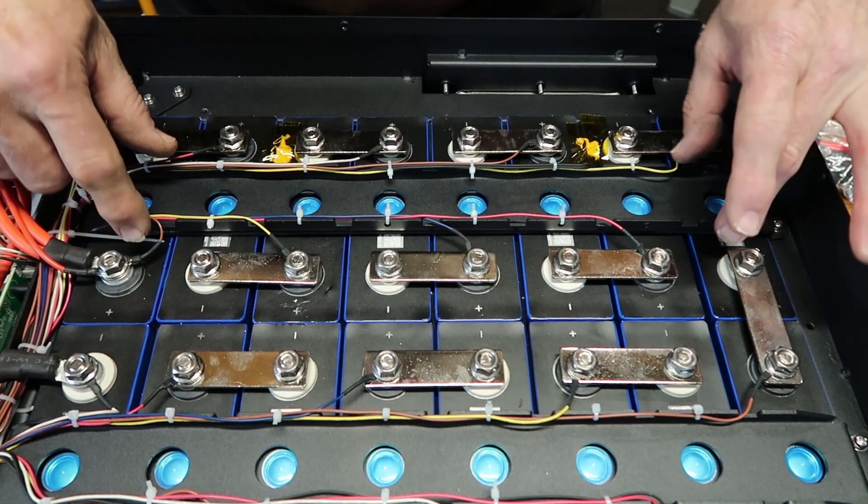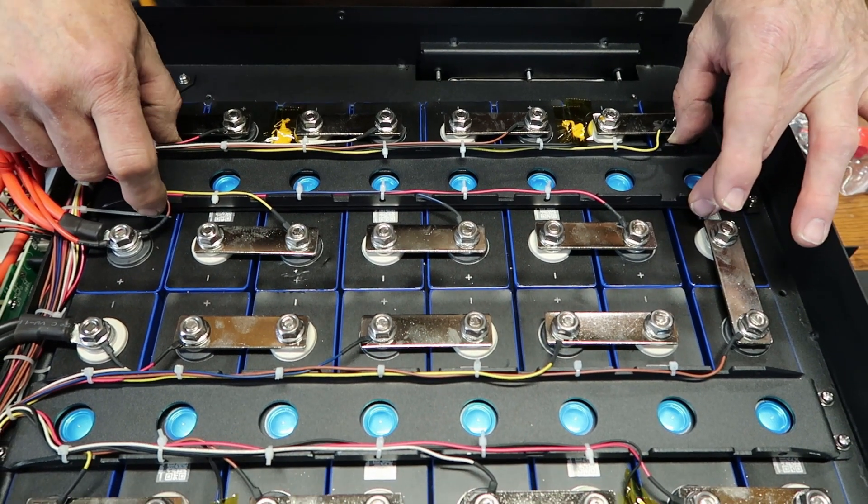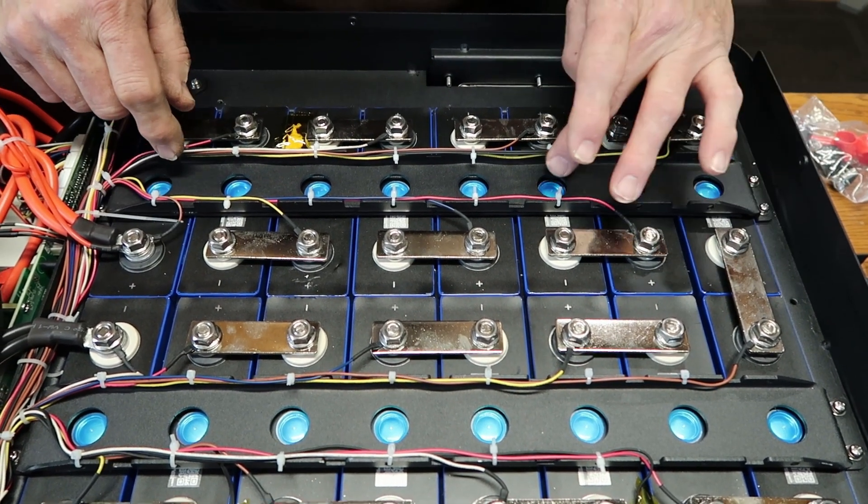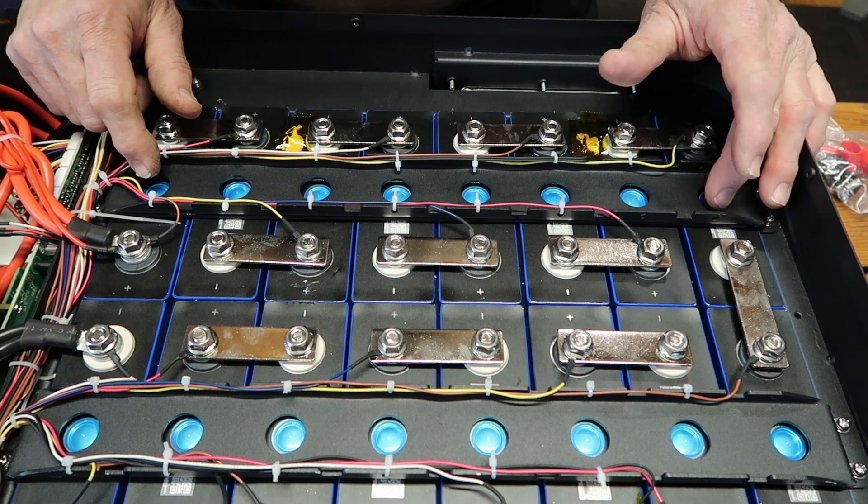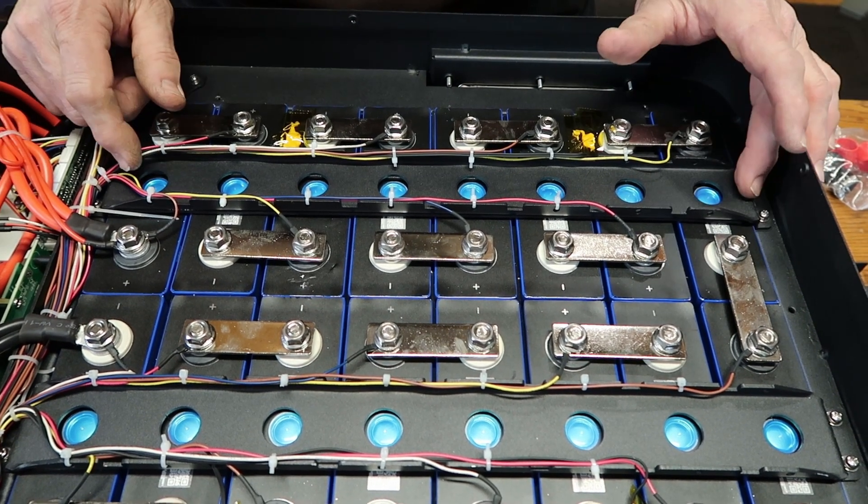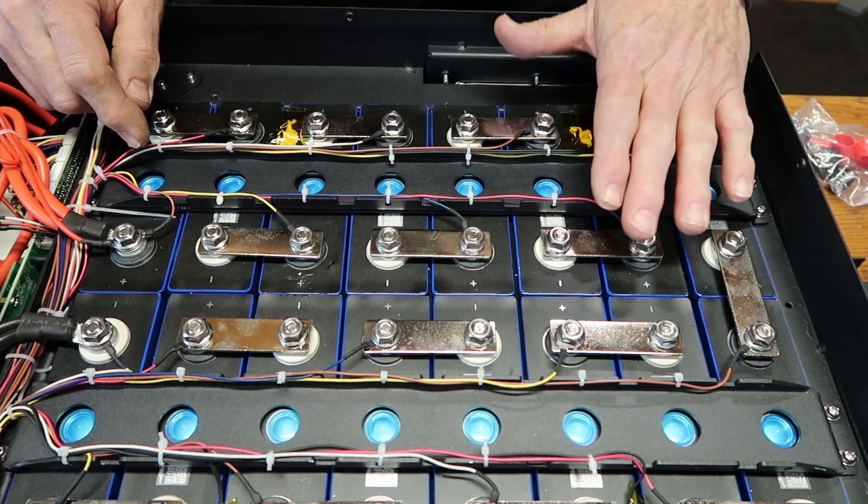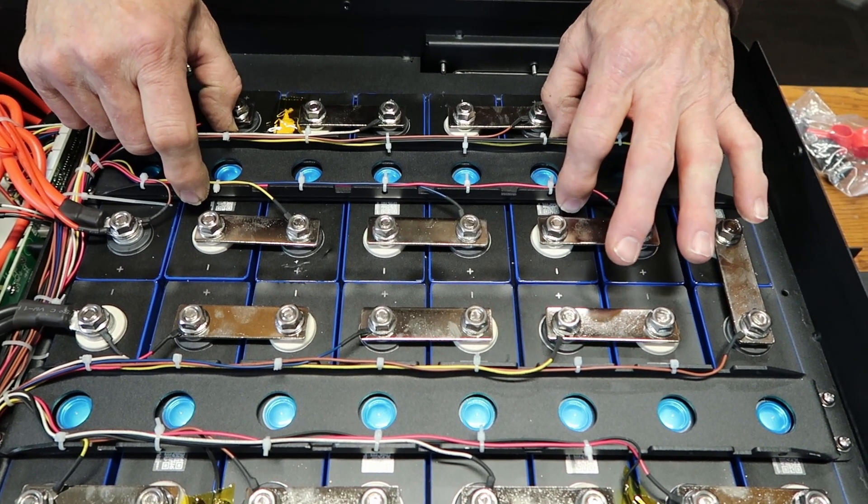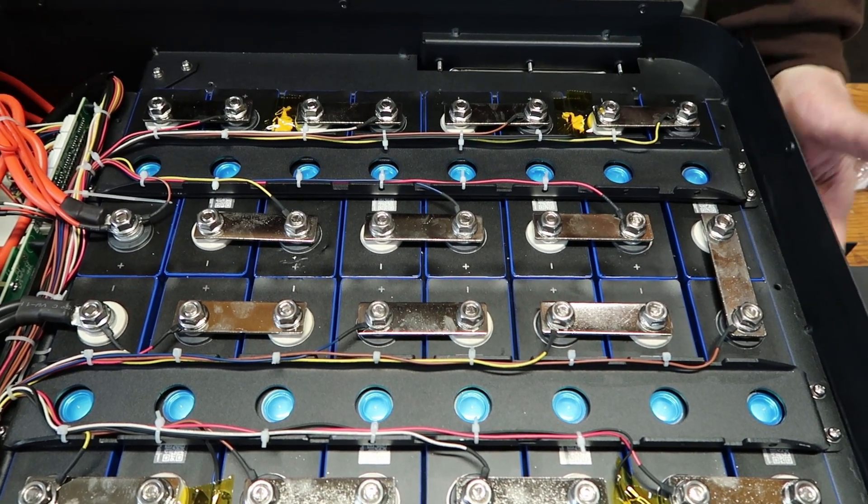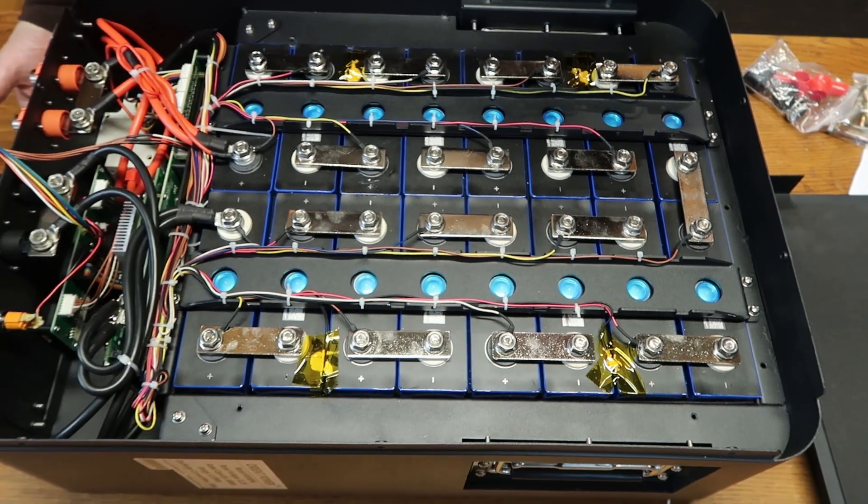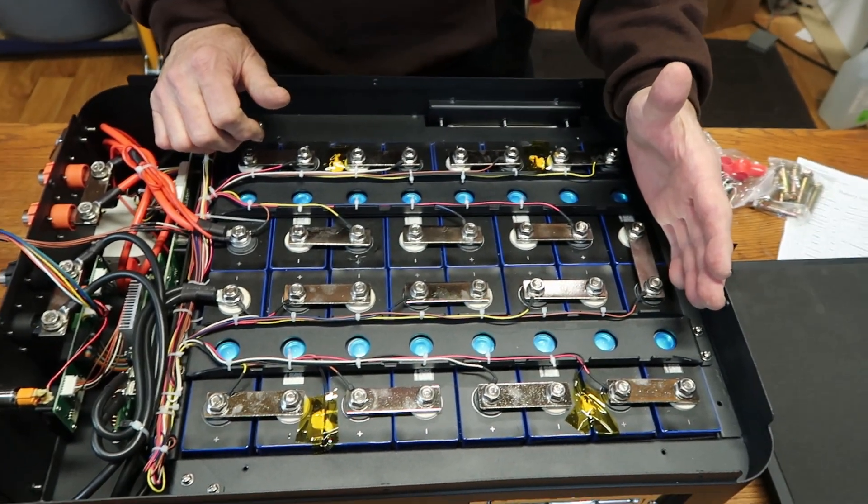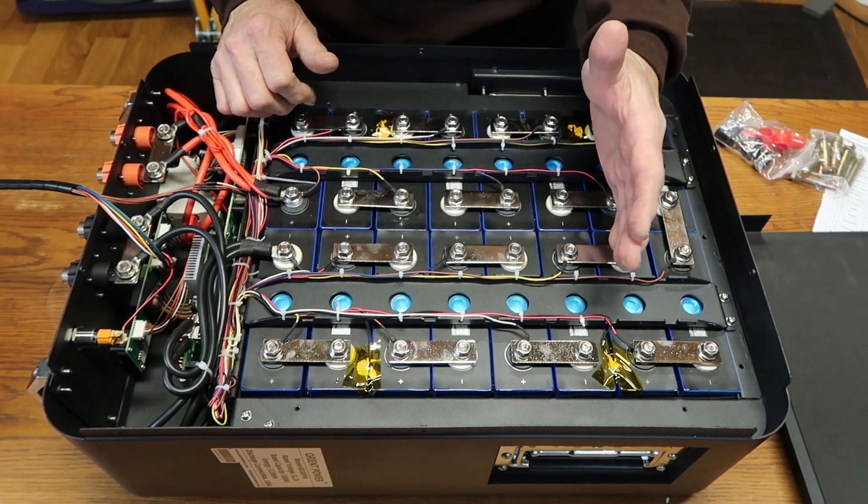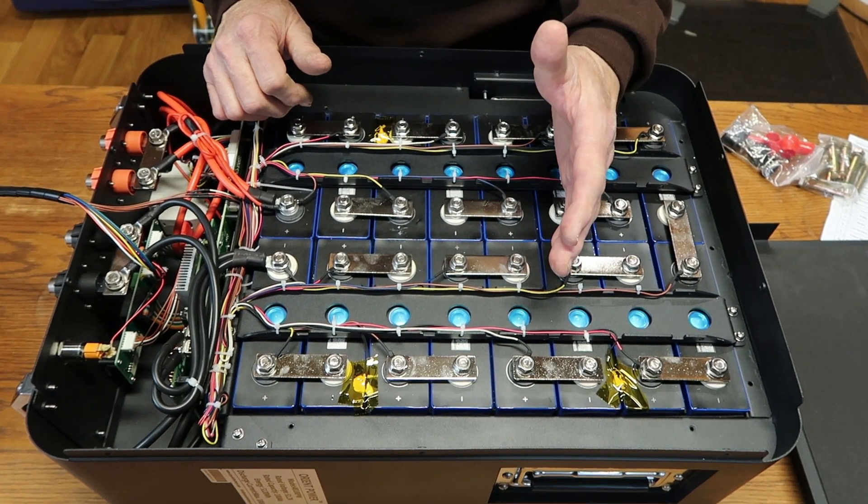As you see, the bars that protect and hold the batteries in place have the appropriate cutout holes for the venting for the individual cells in case that were to happen, which you would hope it never does. But this keeps your pack nice and rigid. This thing's designed to be setting up, so you're going to have some slight compression from the top down on these batteries.